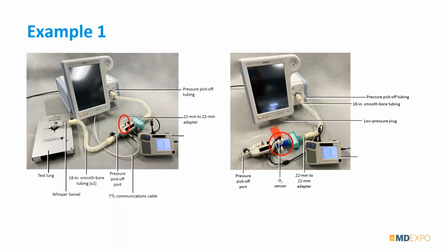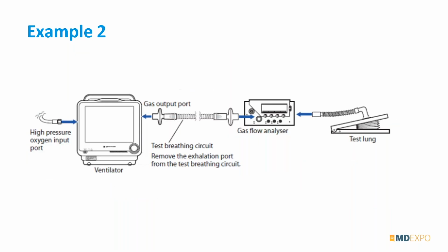The challenge comes when you have to say, okay, I don't have this analyzer. How do I make my analyzer fit into this situation? And we'll kind of help you out with that. Another example, another manufacturer, they did a nice kind of drawing, but they don't really give you any details here as to which ports you should use or what connections you need to make. So again, you might have to really know your test equipment and know how to apply it to this ventilator before you can actually do the test they want you to do.